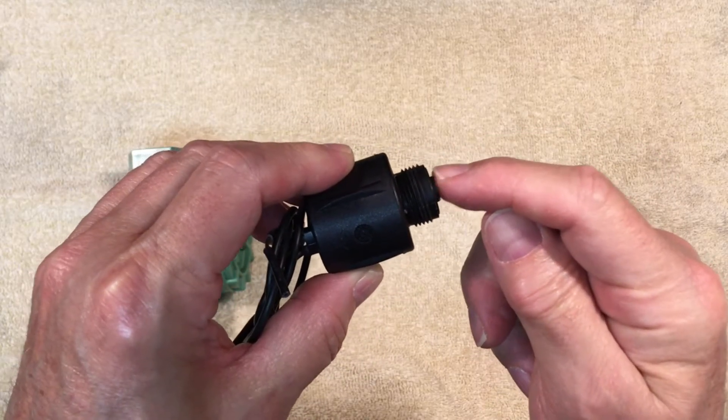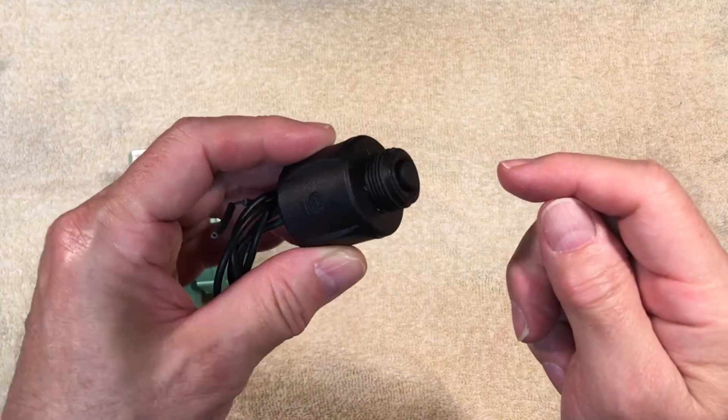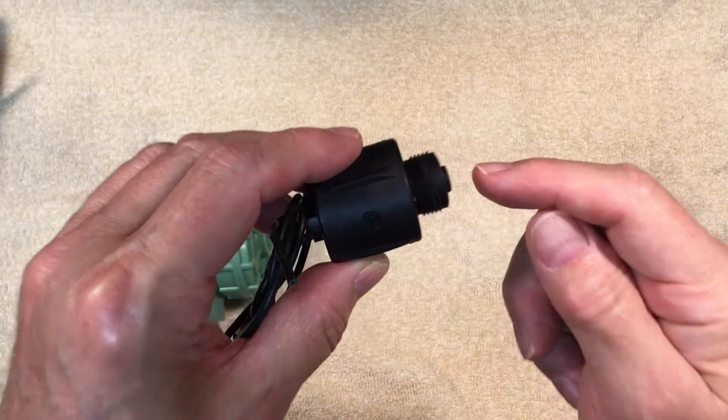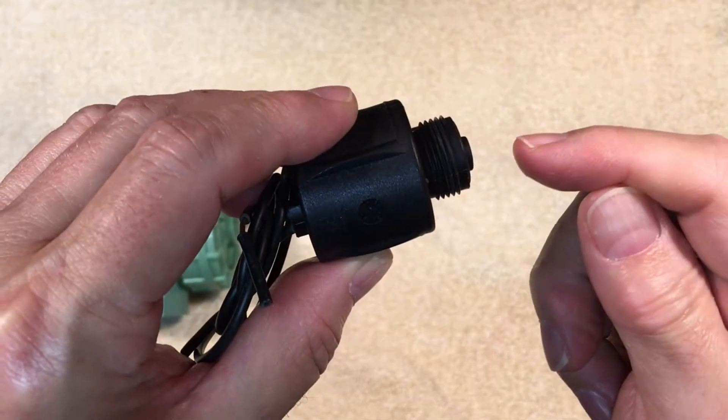When the solenoid is energized with 24 volts AC, the plunger is pulled back up into the solenoid. You can hear it click when it's pulled in. It only moves an eighth of an inch or so.